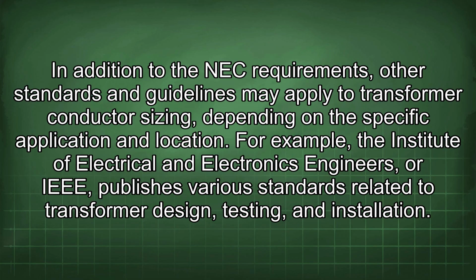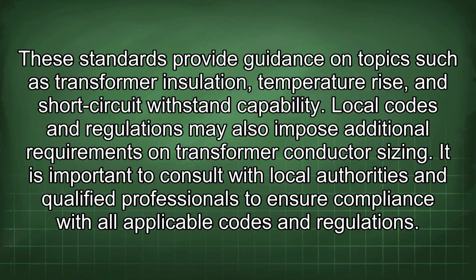In addition to the NEC requirements, other standards and guidelines may apply to transformer conductor sizing depending on the specific application and location. For example, the Institute of Electrical and Electronics Engineers, or IEEE, publishes various standards related to transformer design, testing, and installation. These standards provide guidance on topics such as transformer insulation, temperature rise, and short-circuit withstand capability. Local codes and regulations may also impose additional requirements on transformer conductor sizing. It is important to consult with local authorities and qualified professionals to ensure compliance with all applicable codes and regulations.